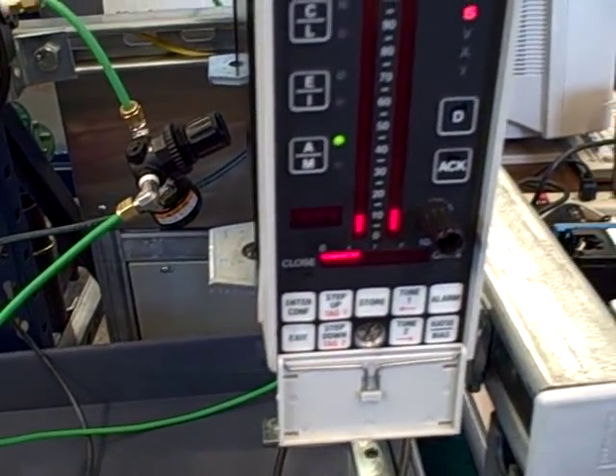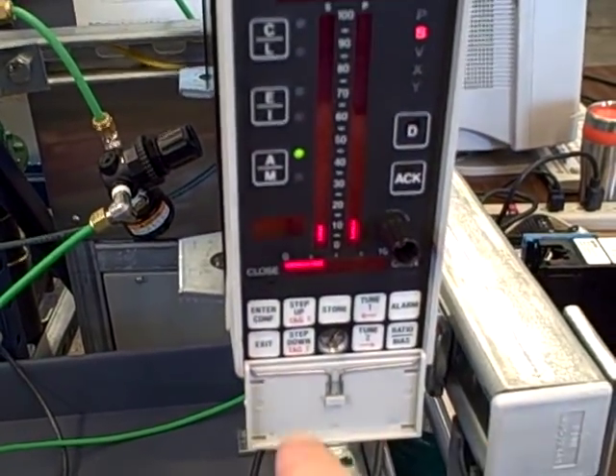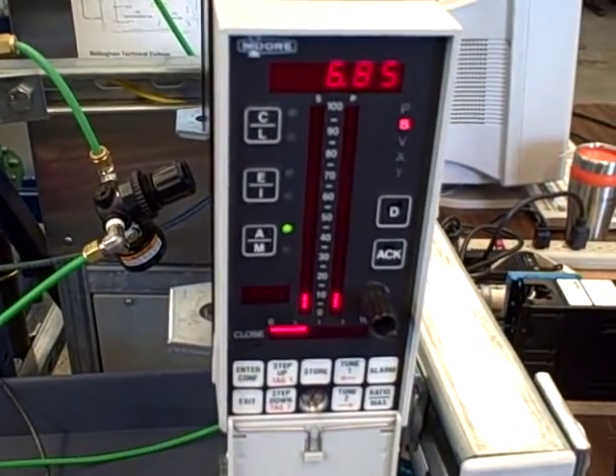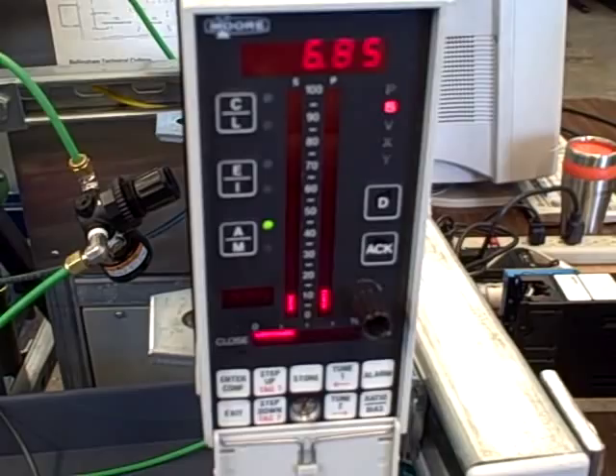Maybe a little bit sluggish with regard to integral, but we're not seeing the huge oscillations at the bottom and sluggishness at the top like we did before with a linear trim valve.